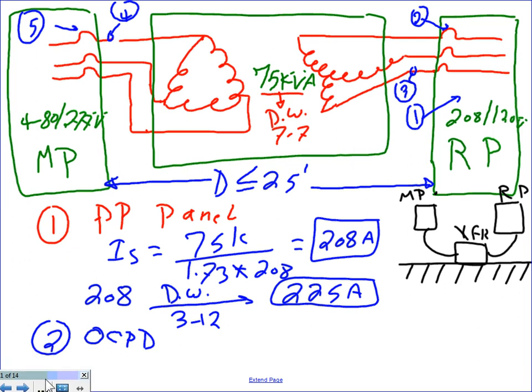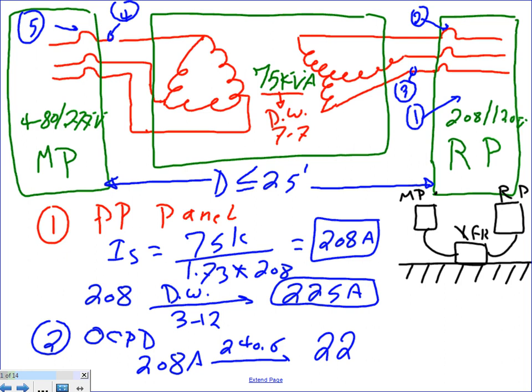The second thing is the overcurrent protection device - the main breaker of the panel. Using the same 208 amps and going to NEC table 240.6, I find 225A is a standard size. The panel rating matches the overcurrent device rating - they're both 225A. The overcurrent device can match the panel rating or be lower, but not higher. So overcurrent protection device = 225A, panel = 225A.